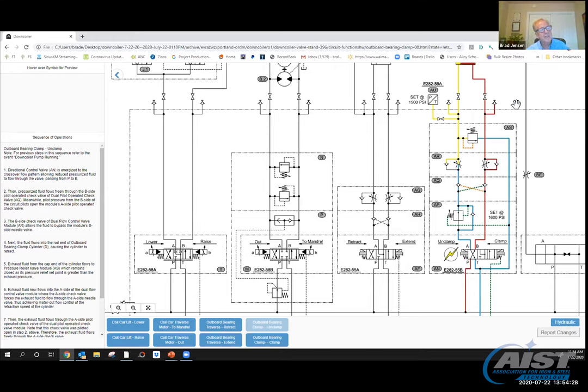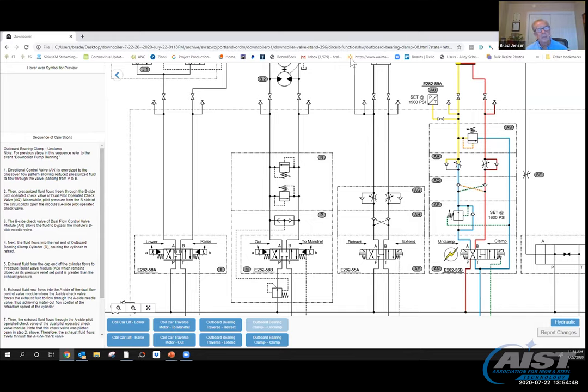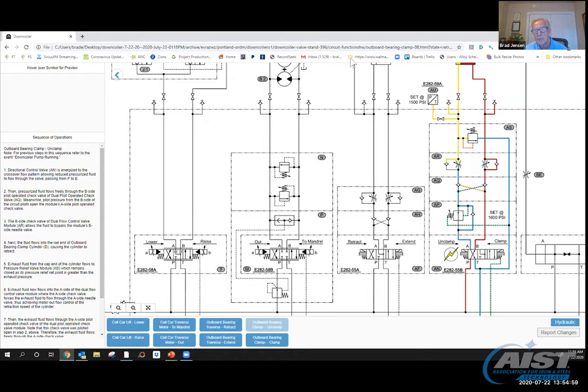I'm checked here. This orifice shows that flow meters across. Anytime you see an arrow diagonally through a symbol, it means it's adjustable. So this adjustable flow control valve is now metering the flow out so it turns from yellow (which is metered) back to blue. This pilot, orange pilot line over here, has opened this check valve so it goes on through the check valve, around the reducing valve, and back to the reservoir. I think we're out of time. I need to stop now to see if there's any questions. I will state that this series of what we're doing here will continue on a regular basis through the year and maybe beyond. I will be using different equipment that you're familiar with as we do this. Charlie, I'm going to turn this back over to you.